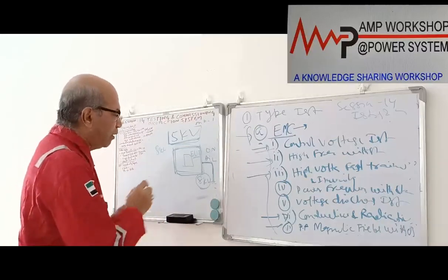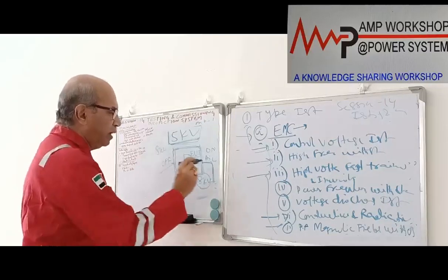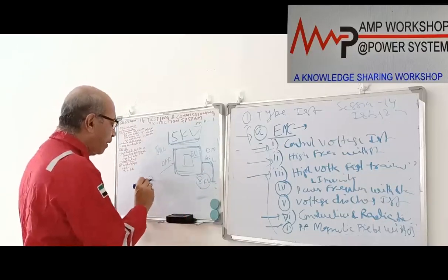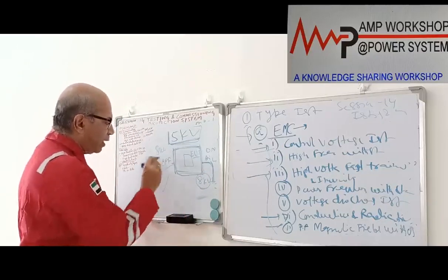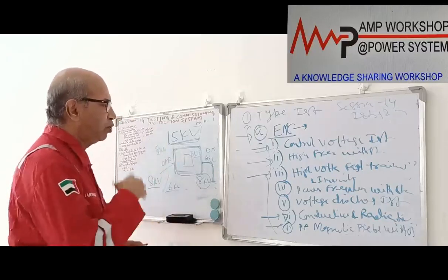Okay. But if the cover is off, it is not on, the cover is separately off. In that case, in the case of insulated cover we give 8 kV voltage, and for contact discharge we give 6 kV. And with this 6 kV voltage it should not maloperate.